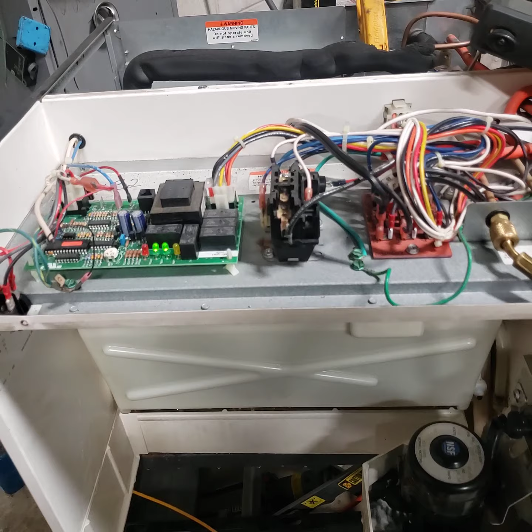Same thing with the ice mode. If after 1 hour the ice mode did not initiate, the probe did not sense ice thickness, it's going to try another 2 times within 3 hours. If it still doesn't sense thickness, it's going to stop.